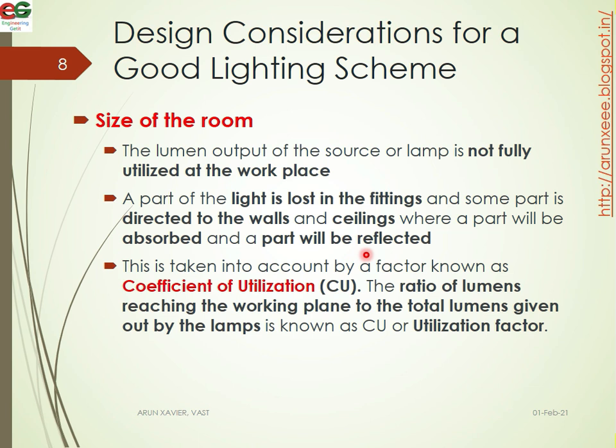This is taken into account by a factor known as Coefficient of Utilization (CU). The ratio of lumens reaching the work plane to the total lumens given out by the lamp is known as CU or the Utilization Factor. The value of CU is typically equal to 0.6 or 0.5.